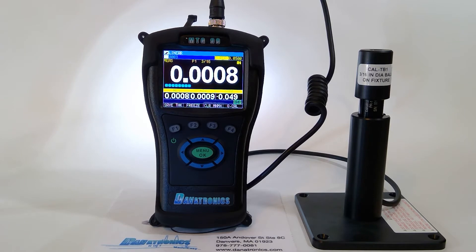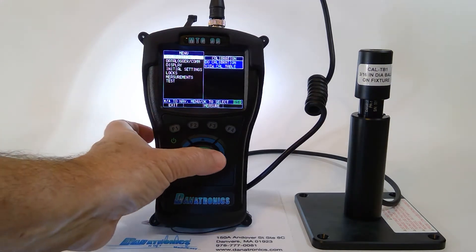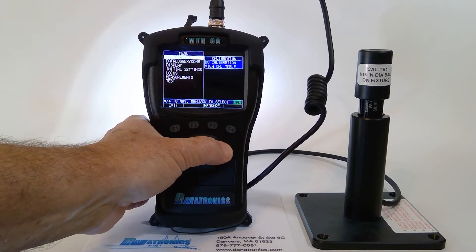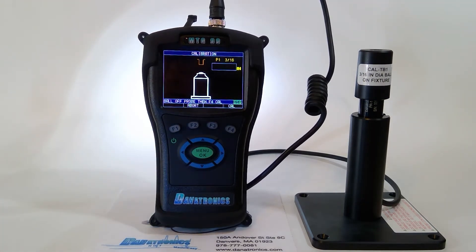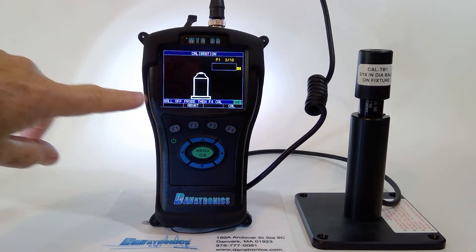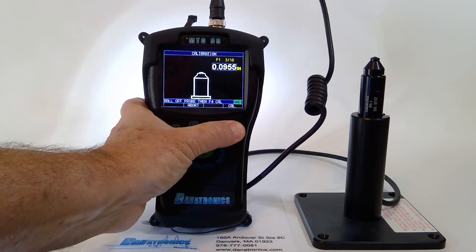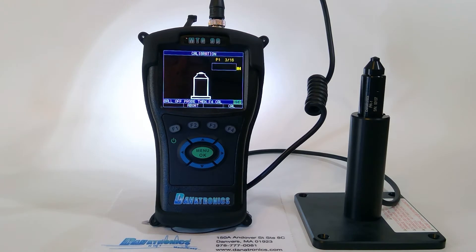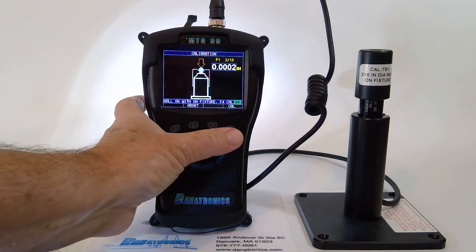Now that the warm-up period is completed, let's do a calibration. To calibrate the gauge, we press the menu OK button, then the right arrow key to go to calibration. We follow the directions on the screen. It says to remove the ball, then press the F4 Cal key. When that's completed, we put the ball on with its centering fixture and press the F4 Cal key.